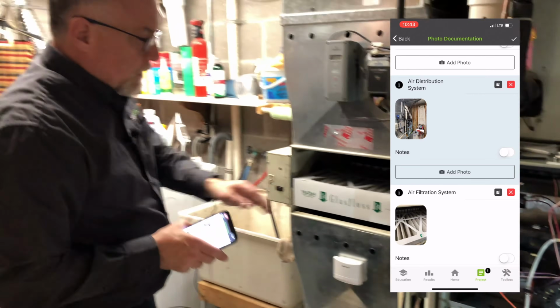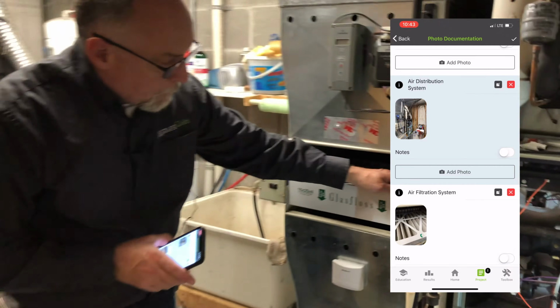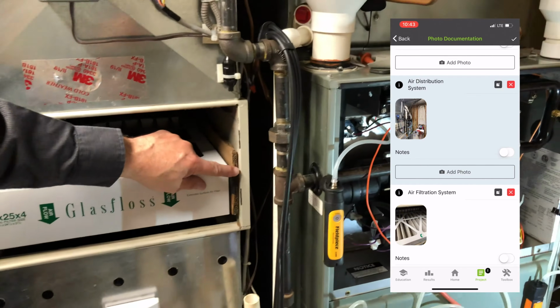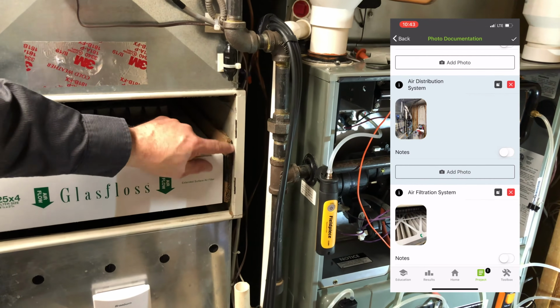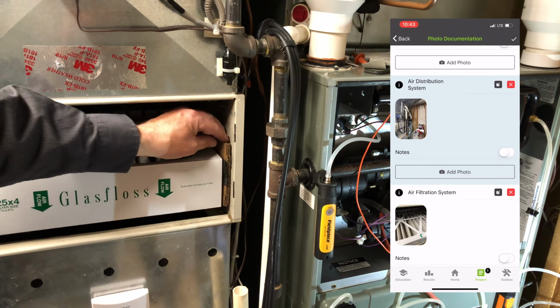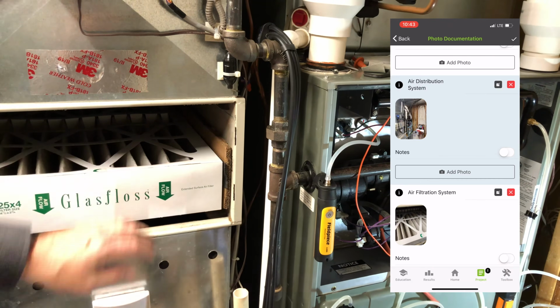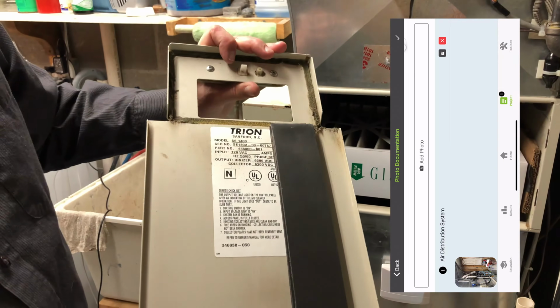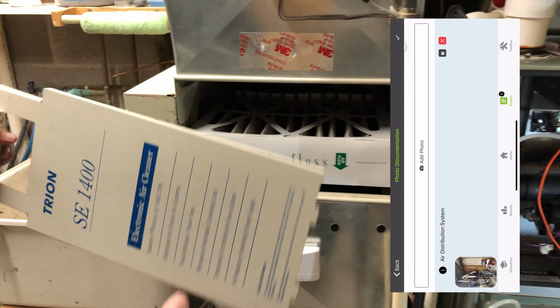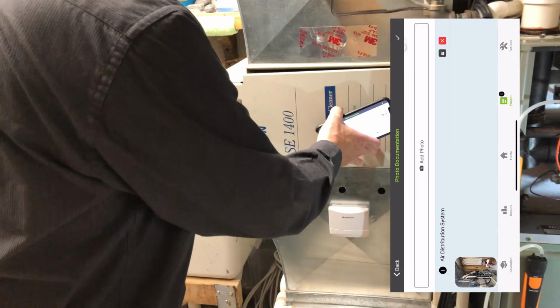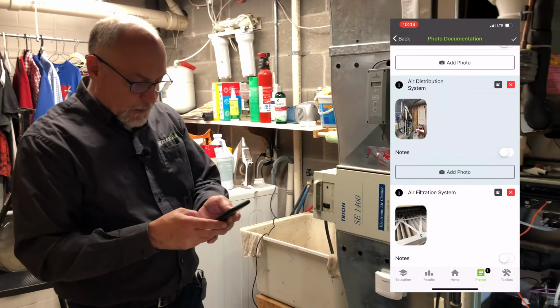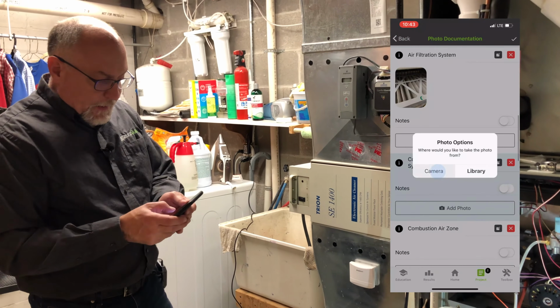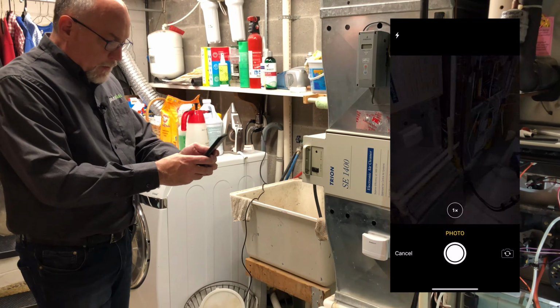And one of the things here, you'll notice too, is you want to make sure that your filters are blocked off. You can see here I put a piece of cardboard with some foam tape on here to lock this filter in. Also on the back of this door, I've got a foam seal to make sure that air's not going around my filter. Air bypassing your filter is a big problem. You want to make sure these doors are sealed and locked on there because you don't want to depressurize your combustion air zone. Condensate drain, again, I'll get a picture here of our condensate drain system.